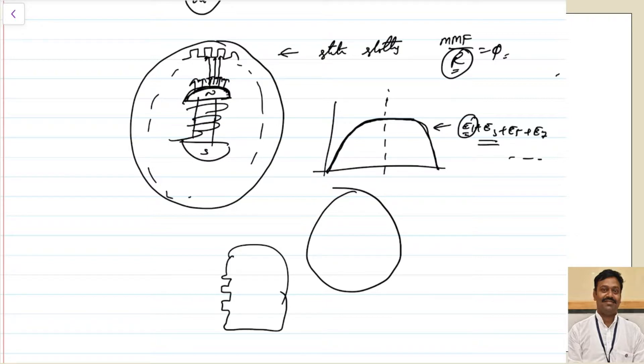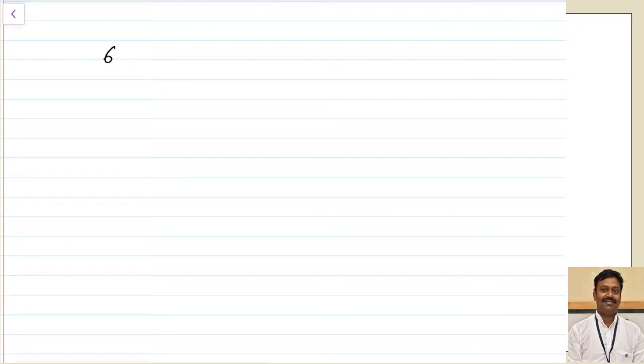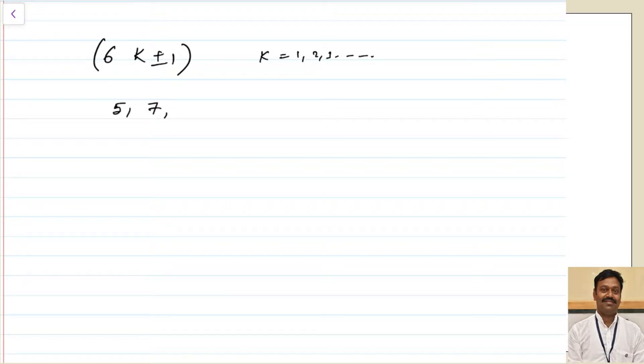The third harmonic component will be suppressed due to our connection diagram — as we have seen during slot harmonics also — because if you are connecting your winding in star or delta connection, that will suppress your third harmonic component in the line, so we are not worried about that. Our major concern is about the fifth harmonic, seventh harmonic, and these components. The harmonics that are produced can be written in the form of 6k ± 1, where k is an integer (1, 2, 3, …). Substituting k = 1 gives 5 and 7; substituting k = 2 gives 11 and 13, and so on.